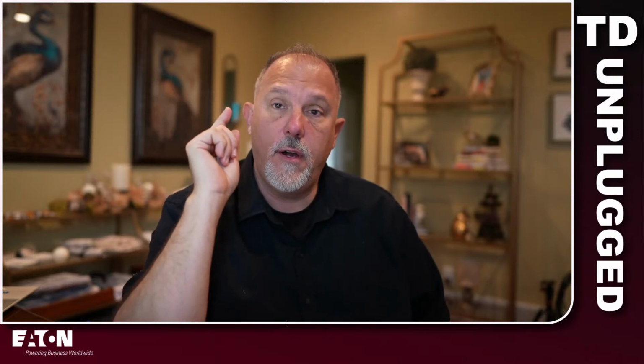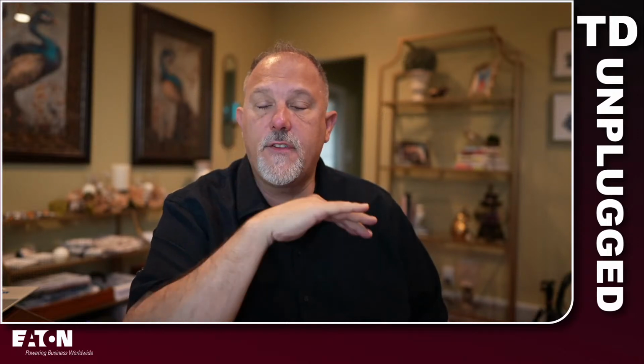And then we do continuous and non-continuous, and then application of adjustment or correction factors. And you have to do those two calculations to determine which one establishes the larger conductor size. You don't have to do that for underground or overhead service conductors. So that's the difference when we get to service entrance conductors. And you'd have to look back at the definition to understand where the service entrance conductors begin and end, right?